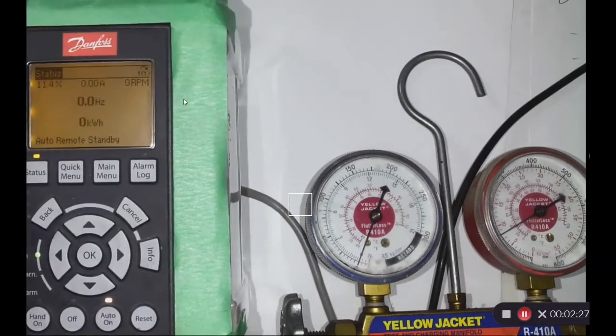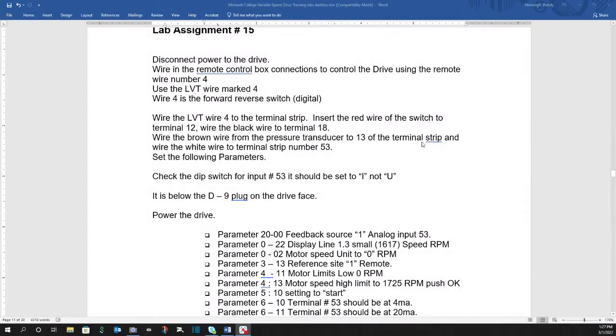So go to the screen now, and with my Word document, you can see now we're just going to wire in two things. Very simple. I've got a low voltage terminal wire coming out of the control box. It's just a digital signal. It's a forward reverse switch. I'm just going to use one normally open switch, and I'm going to put it across 12 and 18 on the terminal strip inside the frequency drive. And for my students, that would be wire number 4.